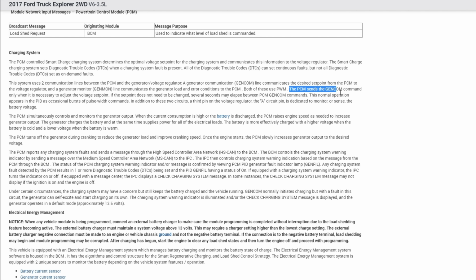The PCM sends the GenCom command only when it is necessary to adjust the voltage set point. If the set point does not need to be changed, several seconds may elapse between PCM GenCom commands. This is normal operation, and it will appear as occasional bursts of pulse width commands.